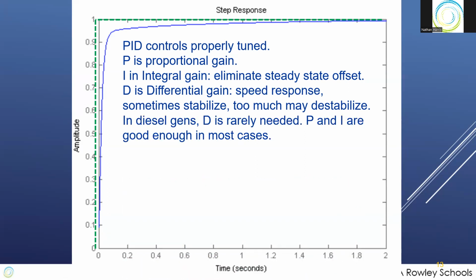In diesel engines, we don't use D a lot unless you get into something specialized. Perhaps marine environments where the load is close to the generator rating. So typically you'll size a generator 1.5 to 2 to 1 to the largest motor. You might end up being closer than that. You might need some D to compensate for that. P and I are good enough. In most cases, a PI regulator is good enough, but sometimes you might need D.